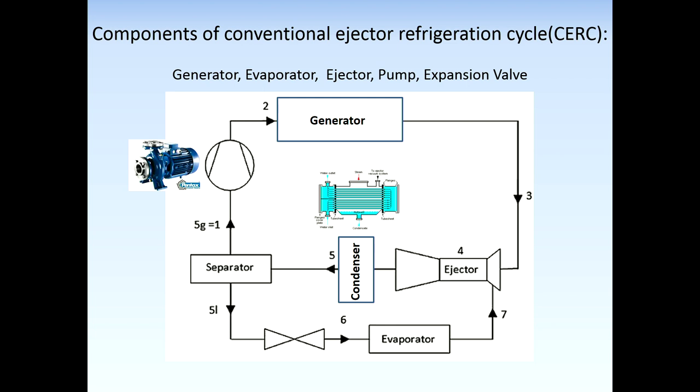The ejector is the heart of the system and is a substitution for mechanical compressors in compression refrigeration systems. It has two essential tasks: first, making the vacuum and discharging the fluids, and second, mixing the fluids. It is a simple model of a vacuum pump or compressor without moving parts; it uses the kinetic energy of a high pressure fluid.